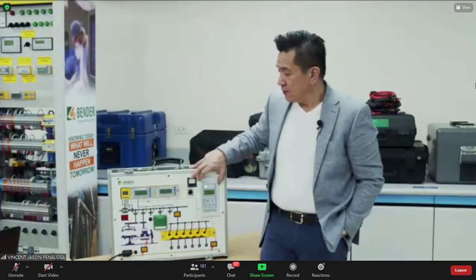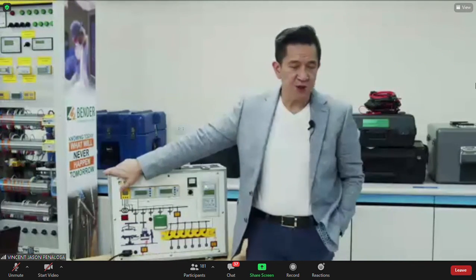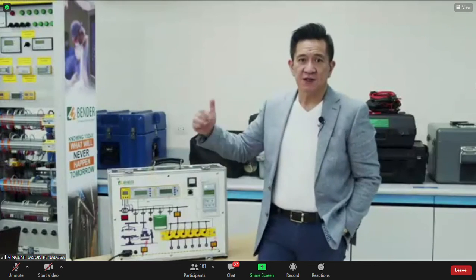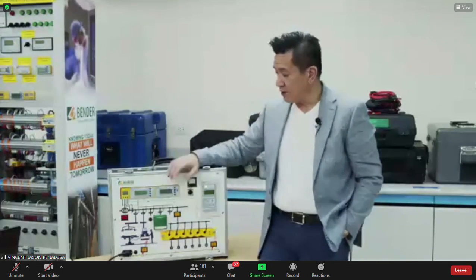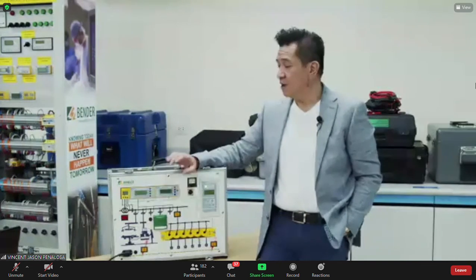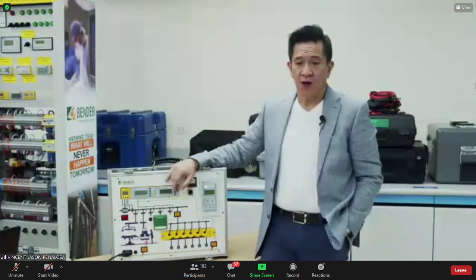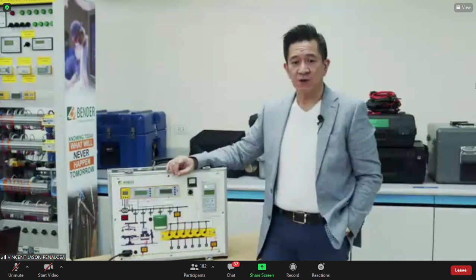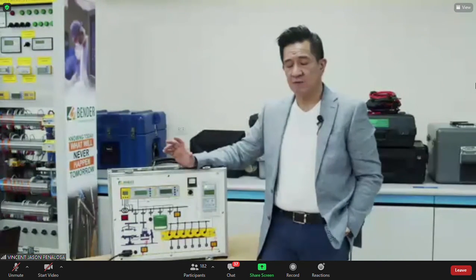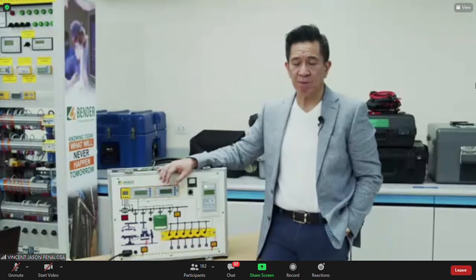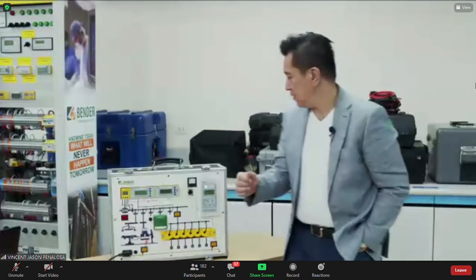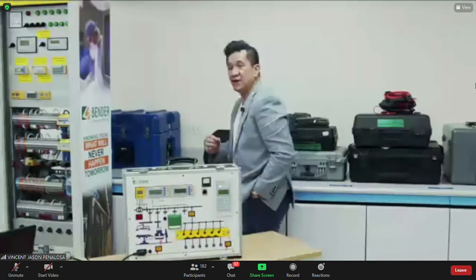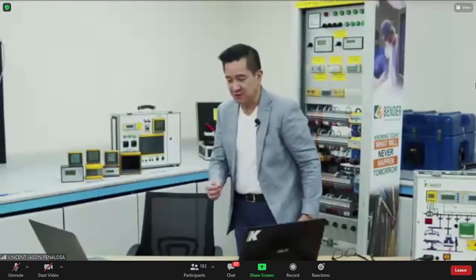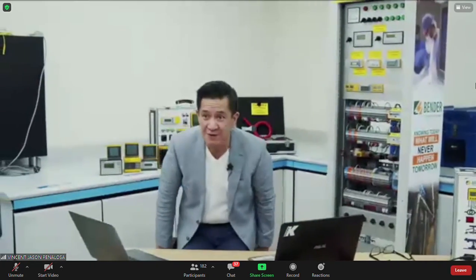Now, transformer, insulation monitoring device, annunciator. But since you're there anyway, though again it's not required, especially if you had a lot of ORs, I would have a gateway. So at any single time there is a fault, the maintenance team, or whoever's in charge of maintenance of your equipment or your electrical system, is informed. Again, your advantage is advanced information here. It's not how good you are at diagnosing a problem. It's you finding out earlier than other people.